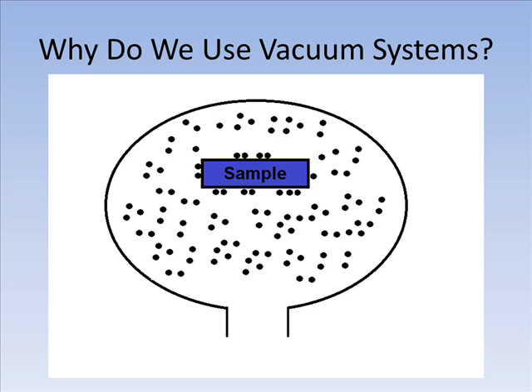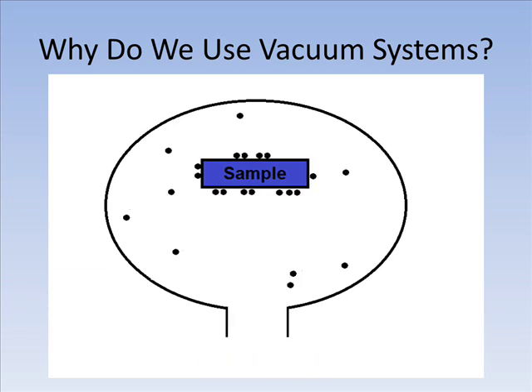To counteract this, air can be pumped out of a closed system. In a chamber at high vacuum, there are few gaseous contaminants to interfere with experimental samples, but samples can still be completely coated with contaminants in just a few seconds. The lower the pressure, the more slowly a sample will be contaminated. At UHV, it can take several hours for surface contamination to take place, making a detailed study of sensitive surfaces possible.